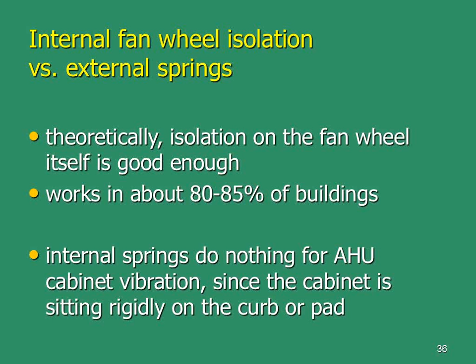This slide. When I first started my career back in the early 80s, this is my 30th year, by the way, it was pretty normal to have an air conditioning unit or packaged air handler sitting on 4, 6, 8, 12, whatever it took, external springs. And about 15 years ago, there was a huge trend to go towards setting the air handler right on the roof and having springs on the internal fan wheel itself. And that works pretty well much of the time.